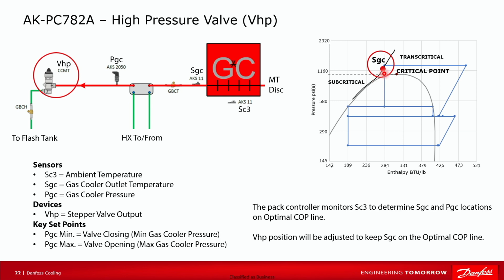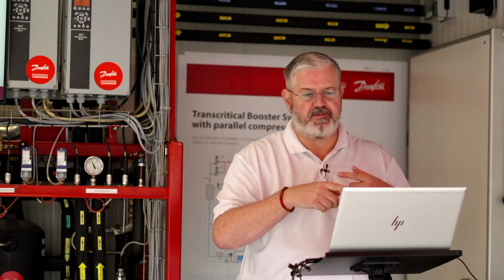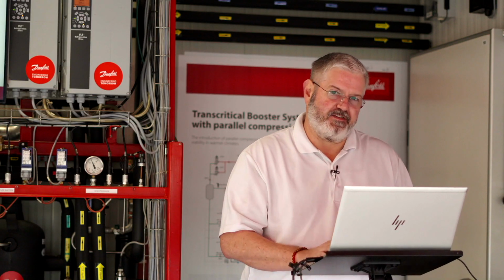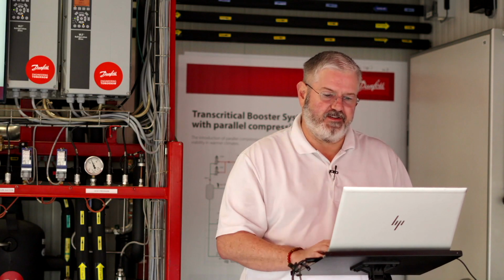And believe it or not, I could be over here and it will close a little to build pressure to bring it back up to that line. Whatever the pressure needs to change to get the gas cooler outlet temp back to the optimal COP line, that corresponding pressure is the setting. All that happens under the hood. It doesn't tell you anywhere what it's thinking. It's doing this hundreds of times per minute, so it is kind of magic. You just give a bottom range, top range.